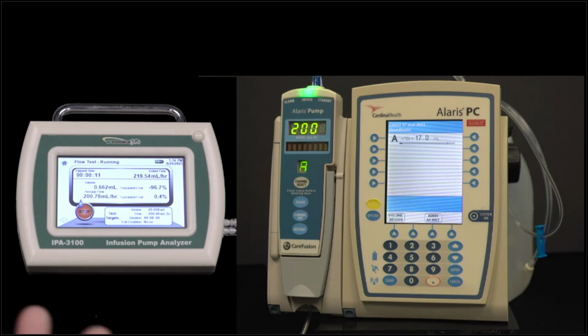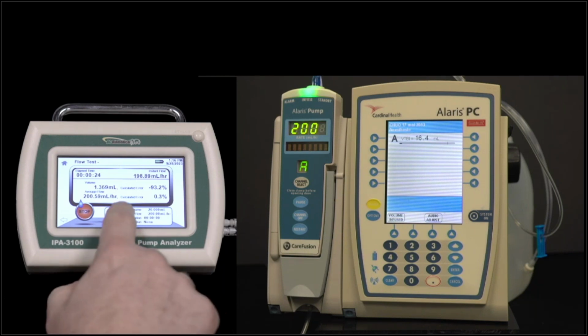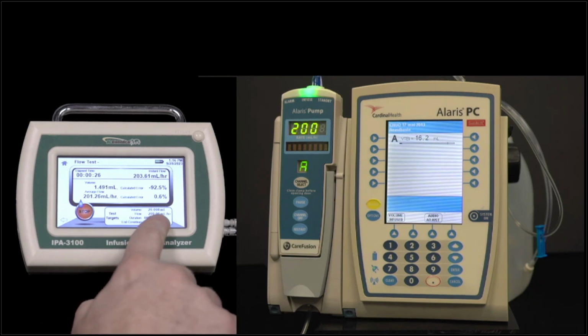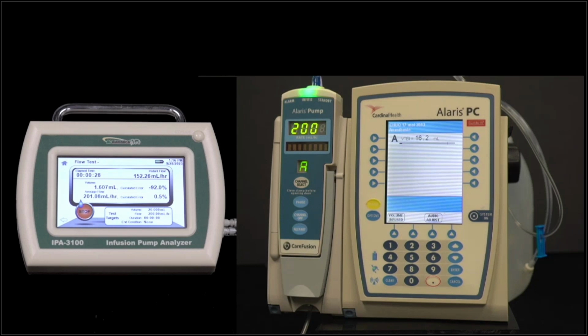If you just want to get quick measurements, just go in and run your test. You can enter in device information, and then you can also enter in your flow and volume, and it'll give you a percent error as it's running. Again, the settings at the bottom of the screen show you how you configured the test, so you know exactly what's going on with this test.